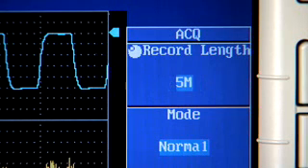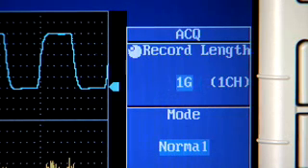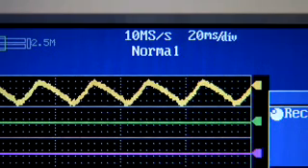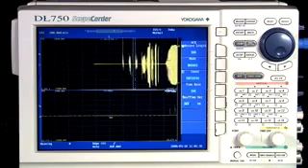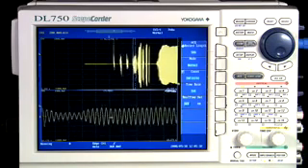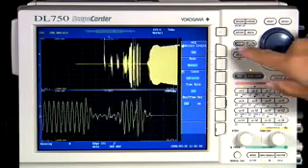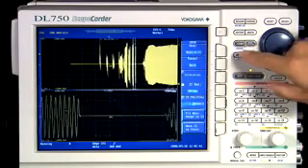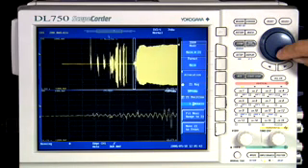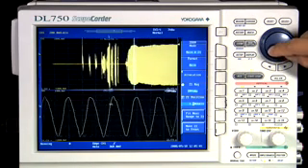Yokogawa perfected deep memory, and the ScopeCorder has its share of it. Up to one billion points of data can be recorded continuously at 10 mega samples per second per channel. Regardless of memory size, the ScopeCorder's GigaZoom engine allows you to smoothly zoom in and out of a signal, even while acquisition is in progress.